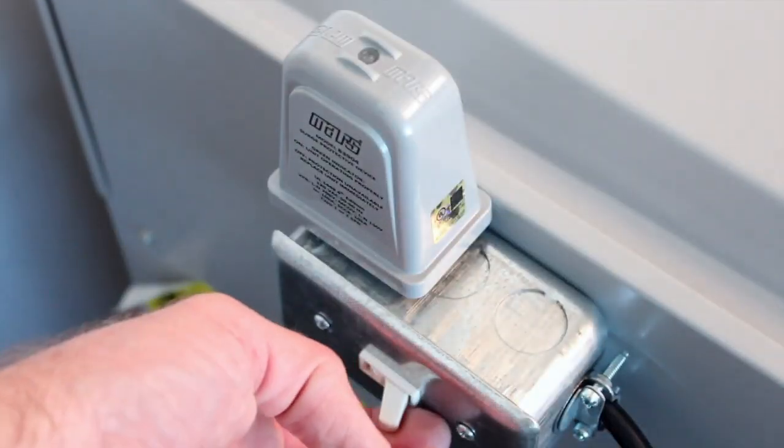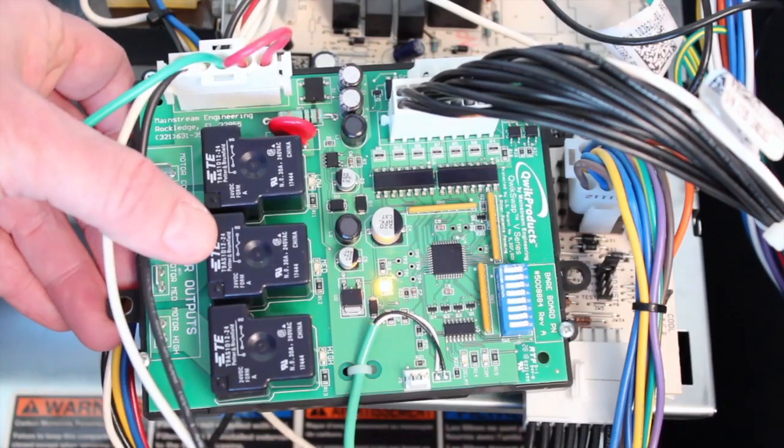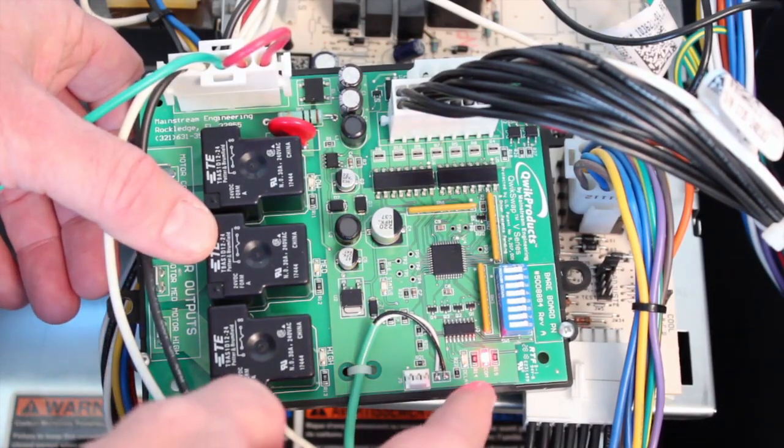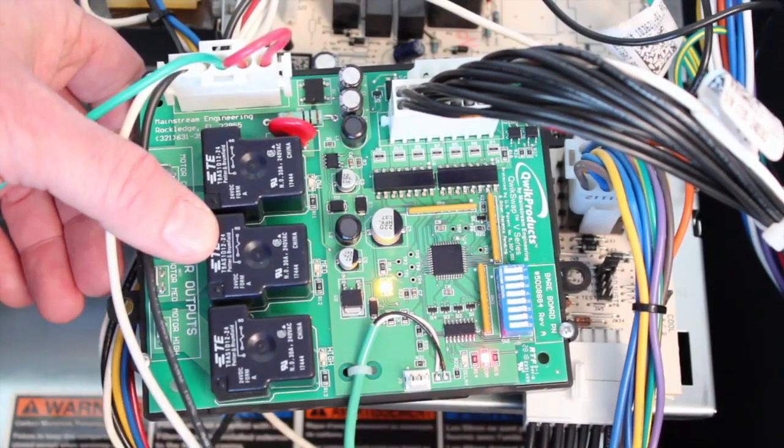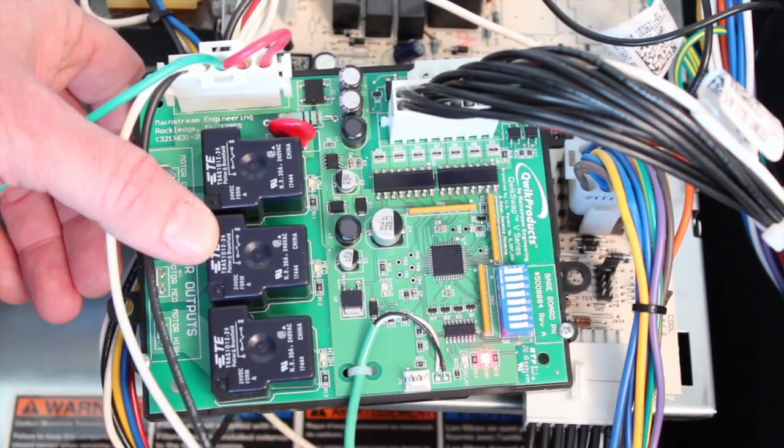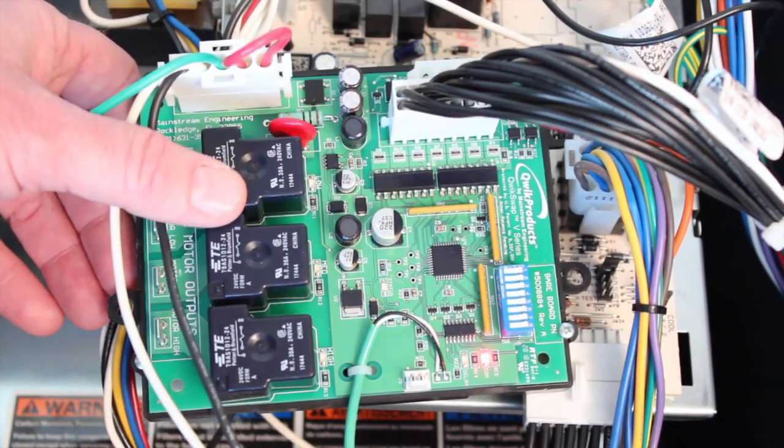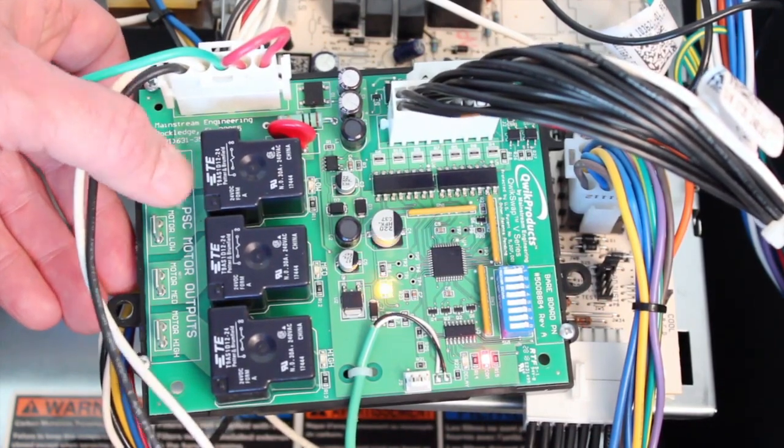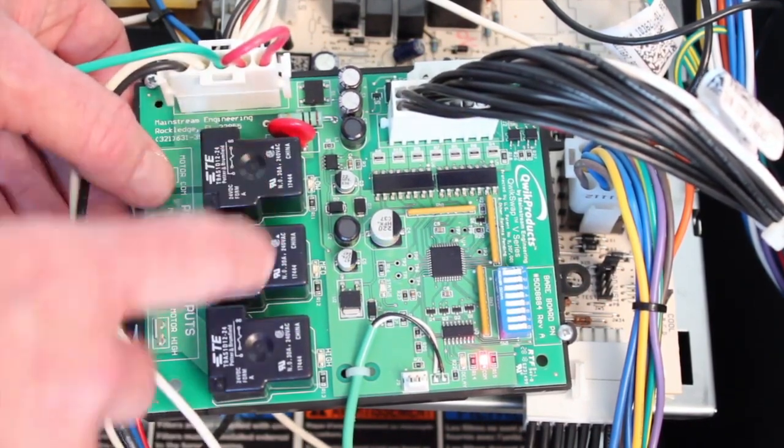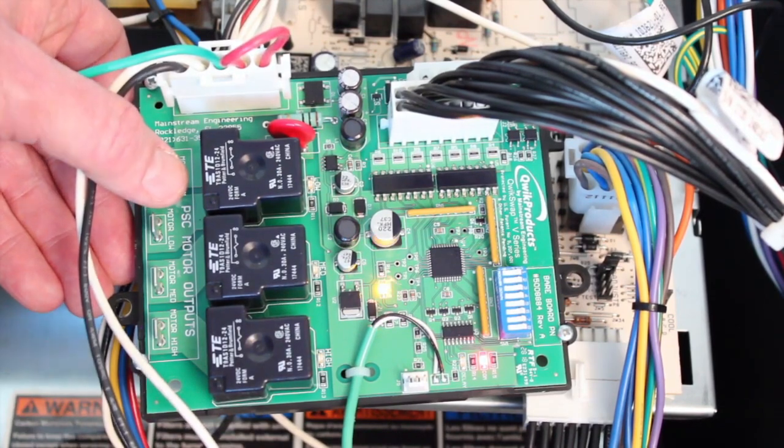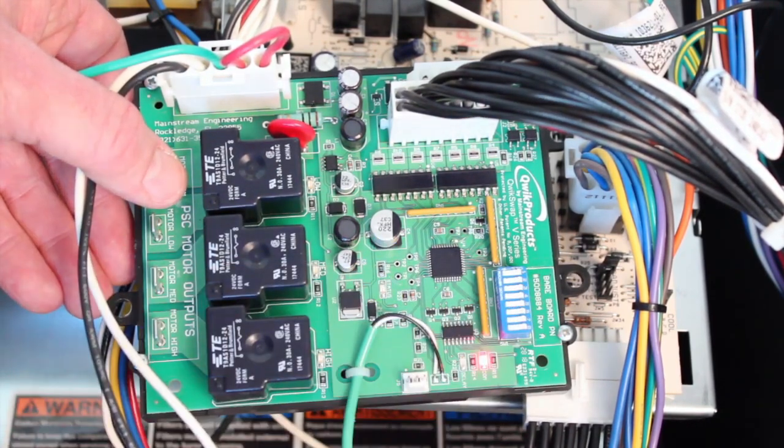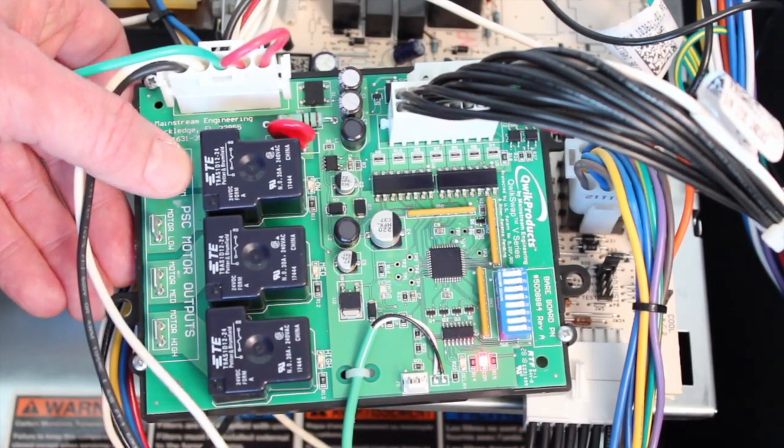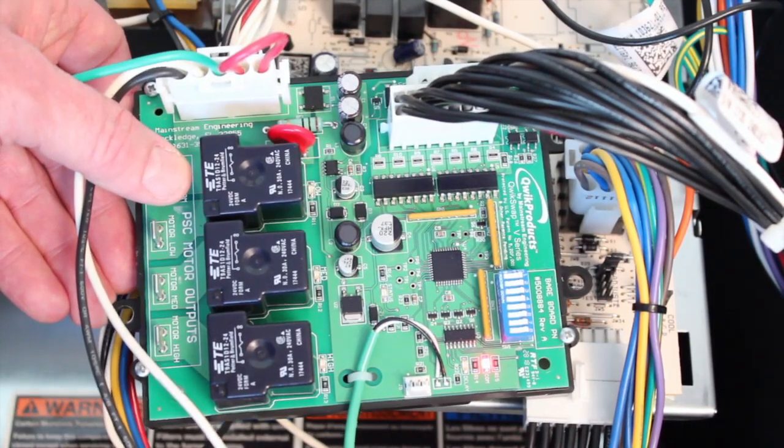Step three, apply power to the system. We have a solid red communication LED and we have a flashing amber LED, which indicates that the QuickSwap board is communicating correctly with the OEM control board. If any of these relays had come on, there's a procedure in the appendix to go through the dip switches to further configure this board. But in this case, we are good to proceed with the motor change-out.